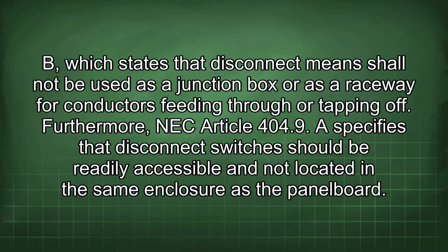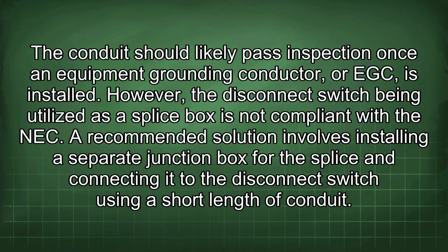Furthermore, NEC Article 404.9 specifies that disconnect switches should be readily accessible and not located in the same enclosure as the panel board. The conduit should likely pass inspection once an equipment grounding conductor, or EGC, is installed. However, the disconnect switch being utilized as a splice box is not compliant with the NEC. A recommended solution involves installing a separate junction box for the splice and connecting it to the disconnect switch using a short length of conduit.